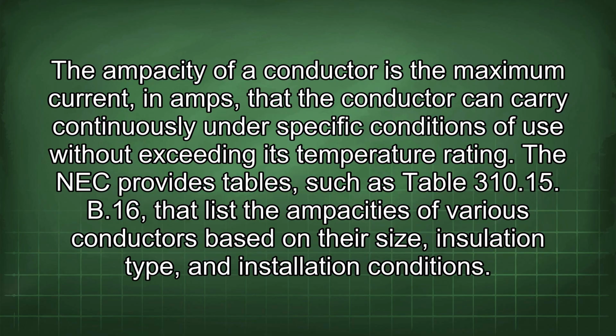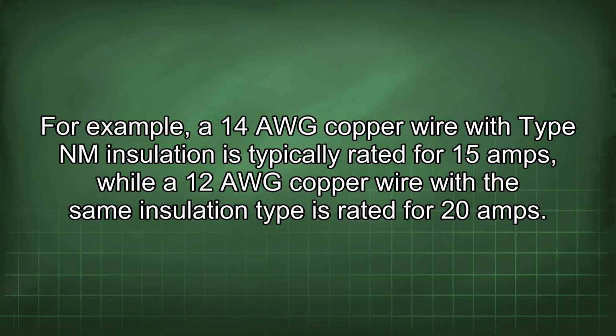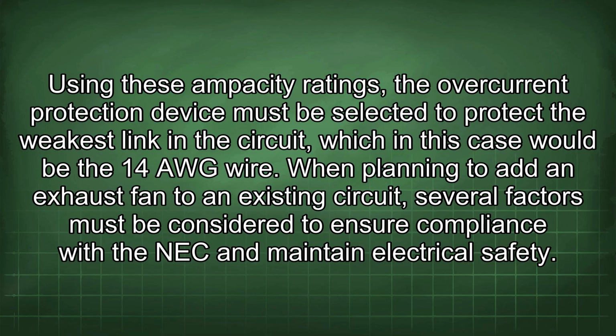The ampacity of a conductor is the maximum current, in amps, that the conductor can carry continuously under specific conditions of use without exceeding its temperature rating. The NEC provides tables, such as Table 310.15(B)(16), that list the ampacities of various conductors based on their size, insulation type, and installation conditions. For example, a 14 AWG copper wire with type NM insulation is typically rated for 15 amps, while a 12 AWG copper wire with the same insulation type is rated for 20 amps. Using these ampacity ratings, the overcurrent protection device must be selected to protect the weakest link in the circuit, which in this case would be the 14 AWG wire.